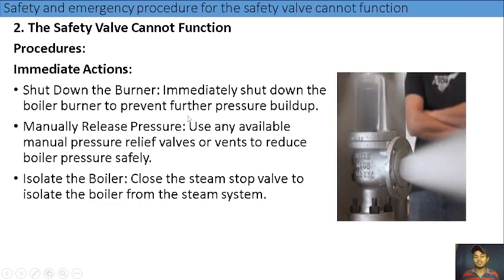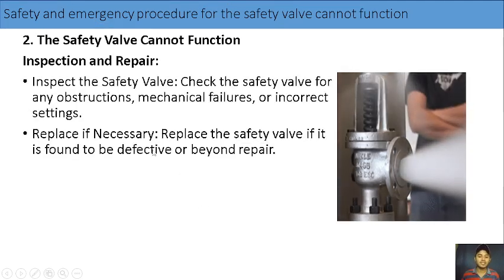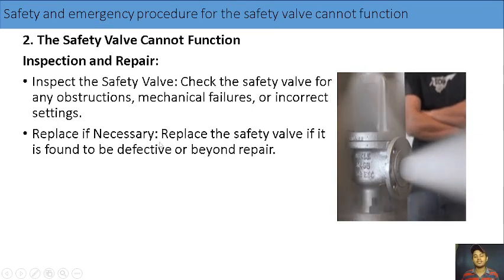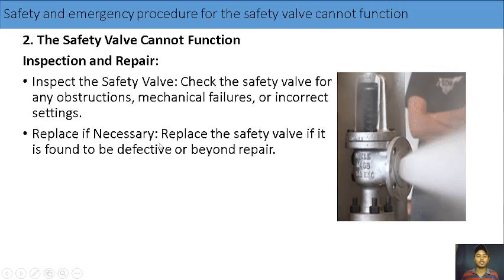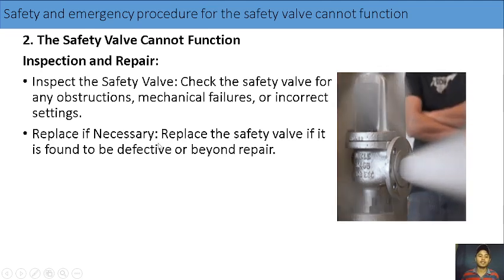So immediate action: shut down the boiler burner to prevent further pressure buildup. Then manually release the steam pressure. Use any available manual pressure relief valves or vents to reduce boiler pressure safely. Isolate the boiler. Close the steam stop valve to isolate the boiler from the steam system. Next, inspection and repair. Inspect the safety valve. Check the safety valve for any obstructions, mechanical failures, or incorrect settings.